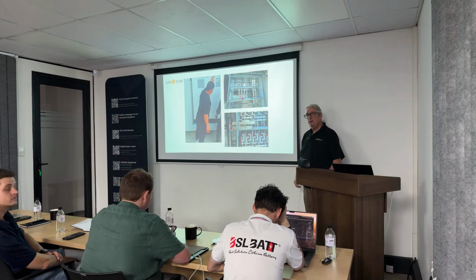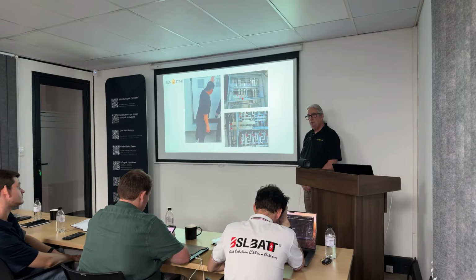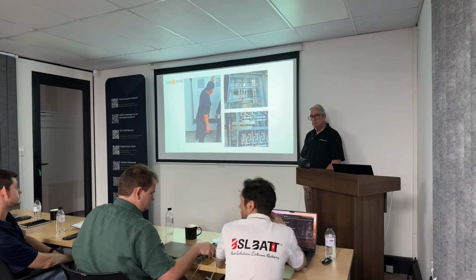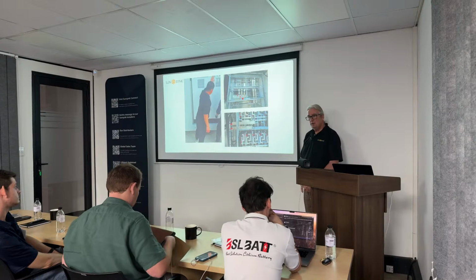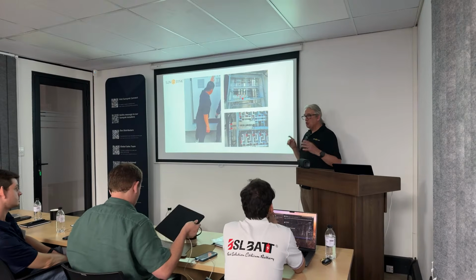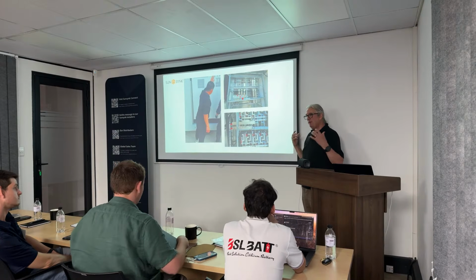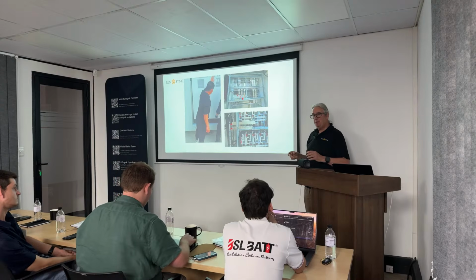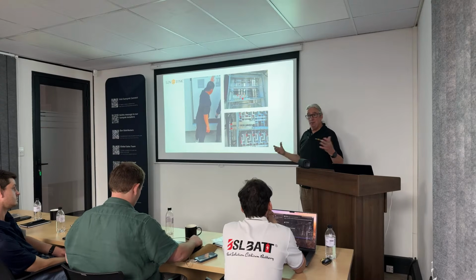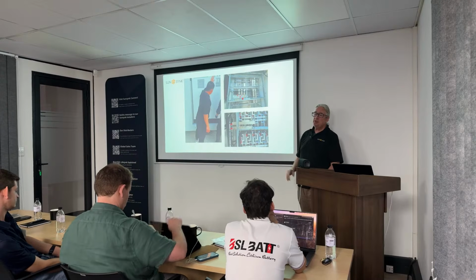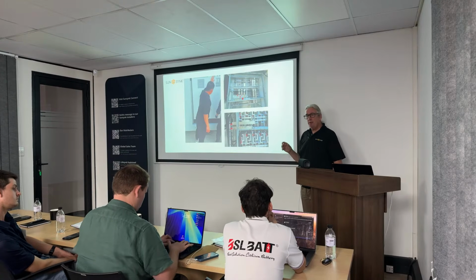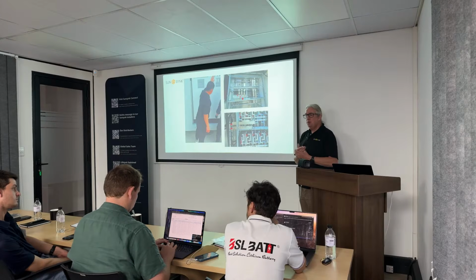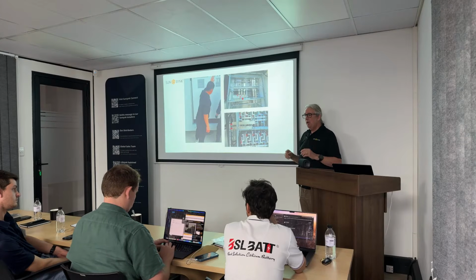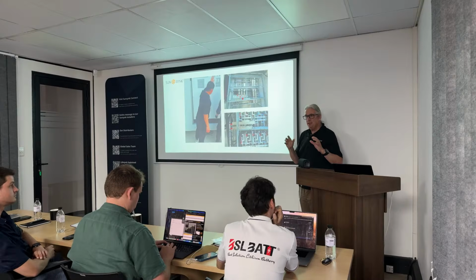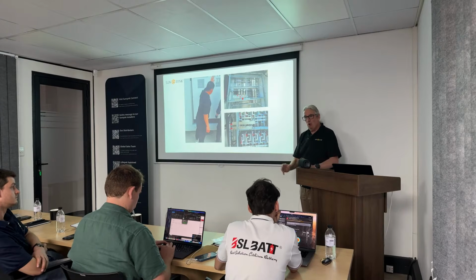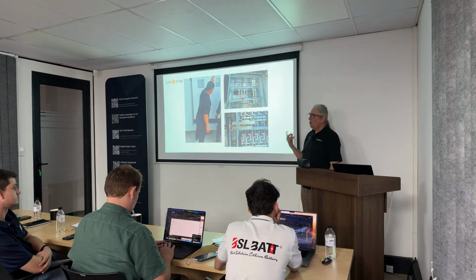In the prior slide, you had PCSs and the MPPTs in the same cabinet. The smaller ones, up to 500 kilowatt, are in the same cabinet because you can't fit them separately. What we're trying to do is have a standard cabinet. So if you buy the 1 megawatt cabinet, we do it as a skeleton, it has so many fitted, but it's got the space to fit more, and it's all pre-configured.